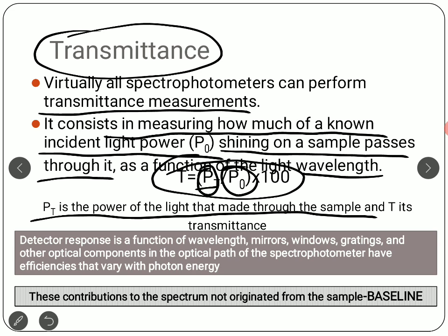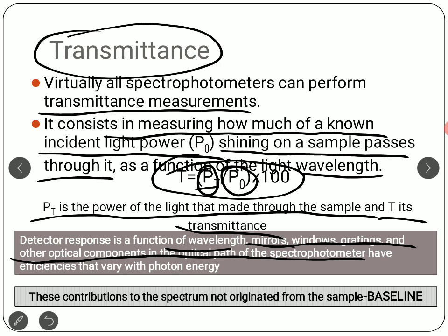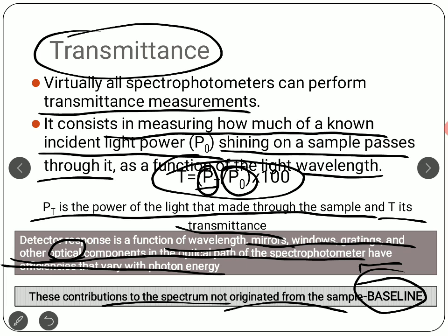The detector responds based on several factors beyond just the sample signal — including wavelength, mirrors, windows, gratings, and other optical components in the spectrophotometer's optical path, including the sample holder or cuvette in UV-visible spectroscopy. These components affect the photon power reaching the sample and detector. Contributions to the spectrum not originating from the sample are called the baseline.